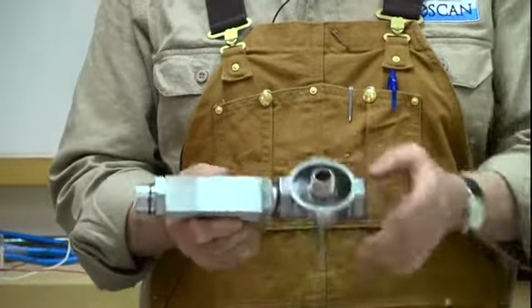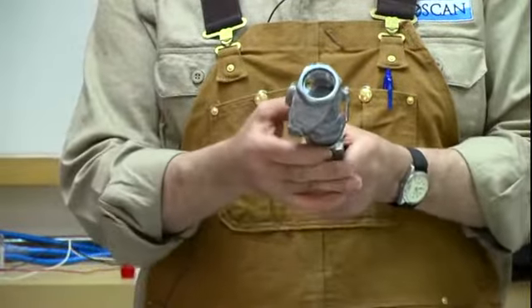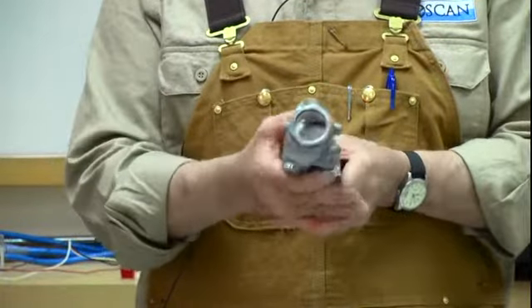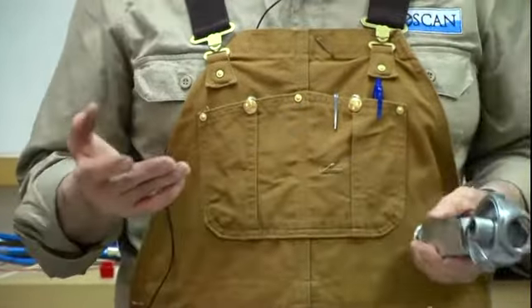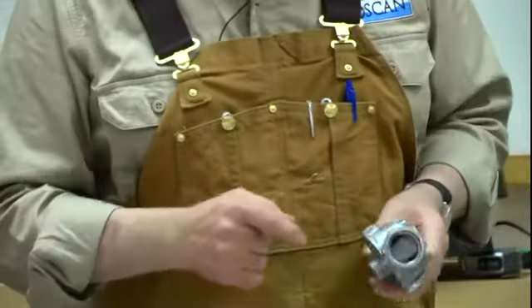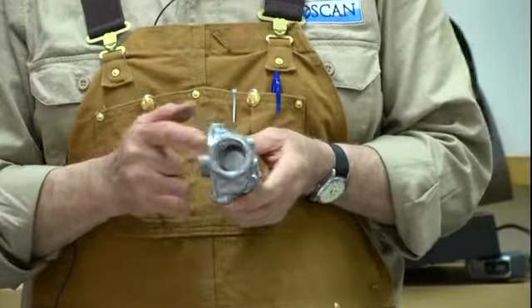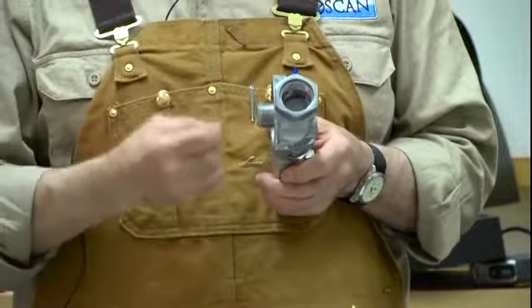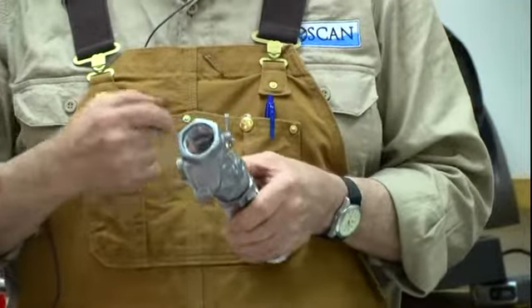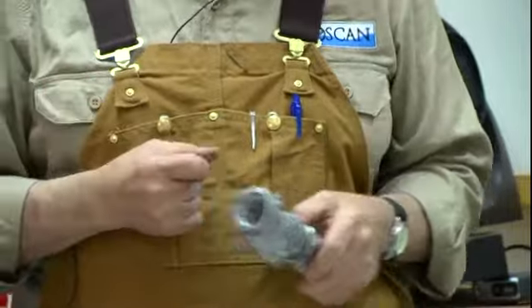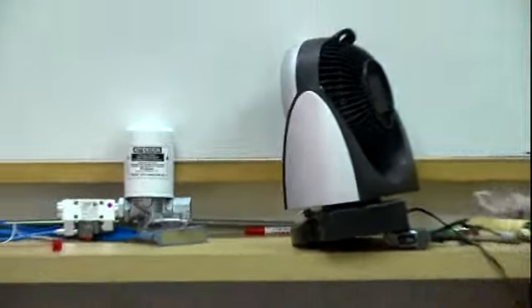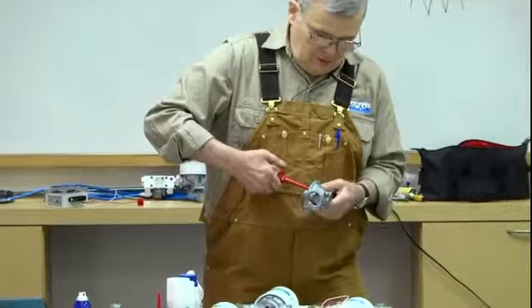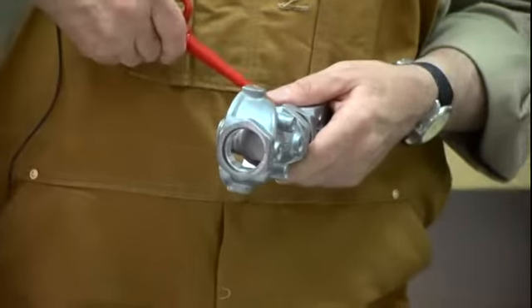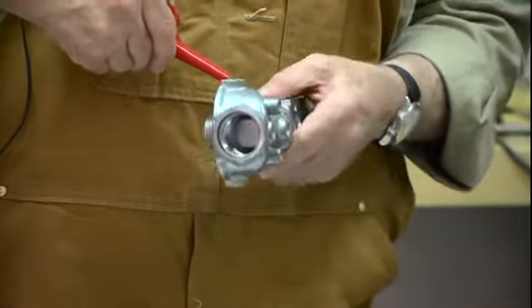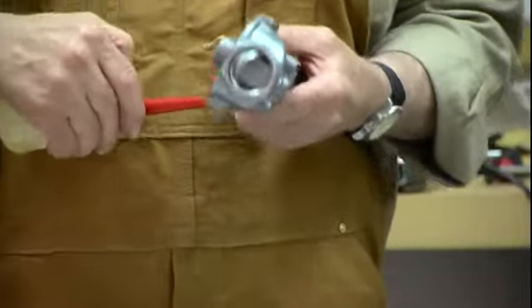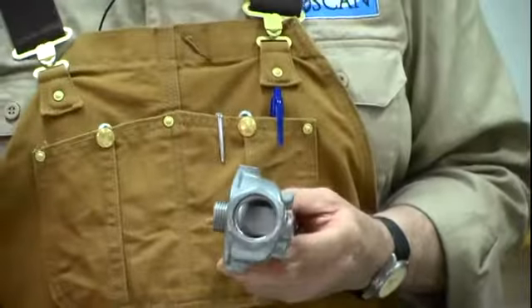To do that, you'll crack the jam nut or the lock nut that holds the casting in place. And when you reassemble it, you need to coat that O-ring with oil. It's very important. If you don't have oil in there, it can bind up and pinch the O-ring, and then it will leak. You should not have to do this often. It should be avoided, but if you have to, you can. You just have to be careful.